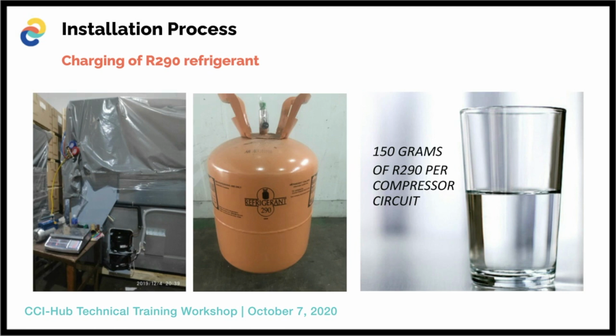Before charging the R290 refrigerant into the system, we follow 2 steps. Number 1 is preparation of the basic tools and materials needed for installation, such as oxygen-free dry nitrogen, micron gauge, pinch-off tools, shut-off valves, refrigerant hose and gauge, weighing scale, and especially combustible gas leak detectors, and most of all, vacuum pumps. The second part is the mandatory use of personal protective equipment, or PPE.